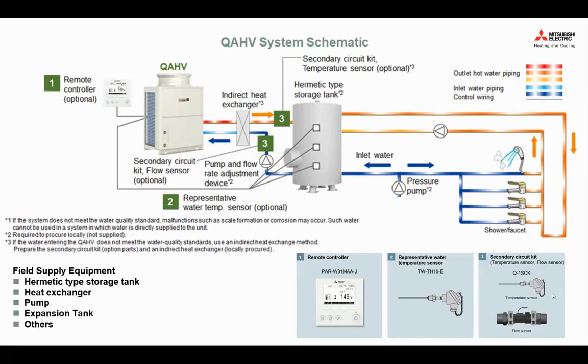And obviously, as with most things in life, as water is heated, it will expand. So the designer will need to design or specify an expansion tank to accommodate the change of water volume. And along with other components, mixing valves, faucets, right? And then the shower head and all that stuff needs to be procured locally to meet code. And I think most of us will need to select, let's say, a high-efficiency shower head, with a certain flow rate, I believe 2.5 GPM or 3.5 GPM. I cannot recall, but that is the specification for a shower head. Yeah.